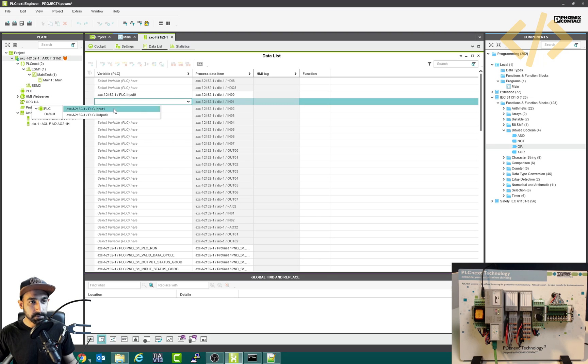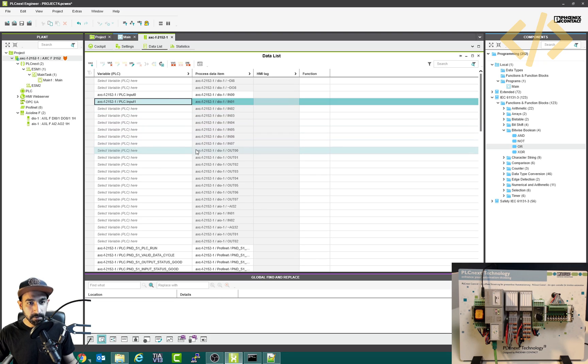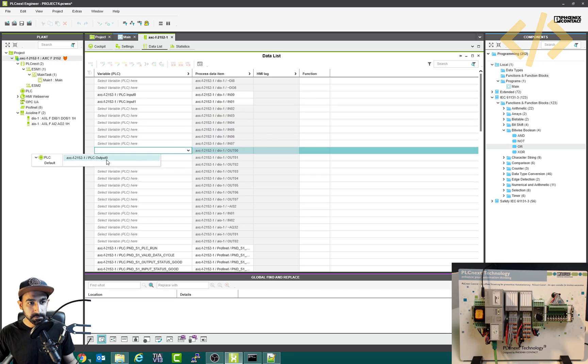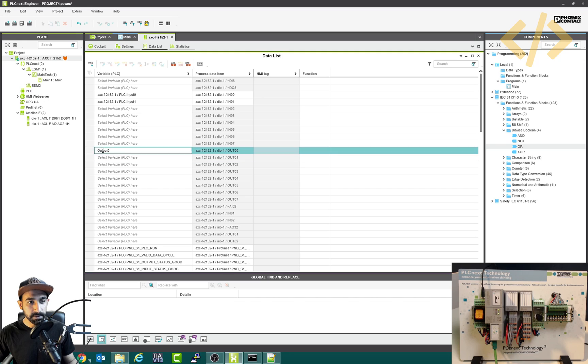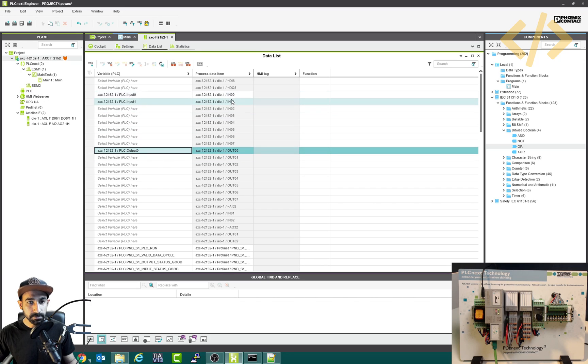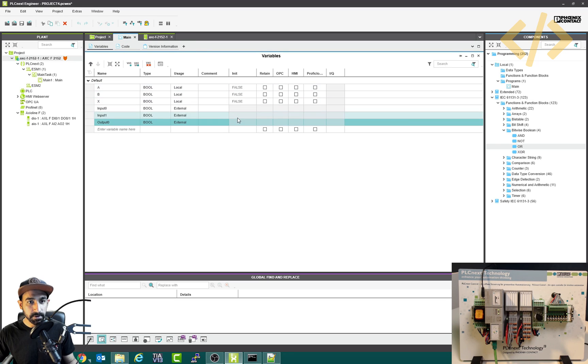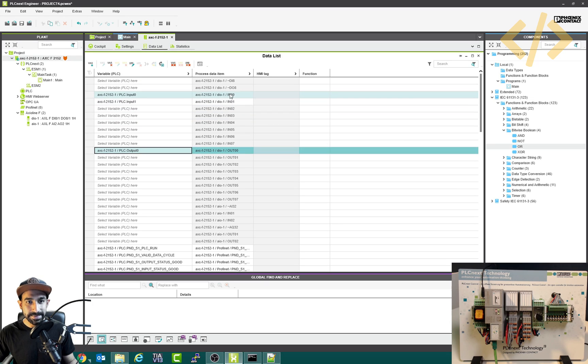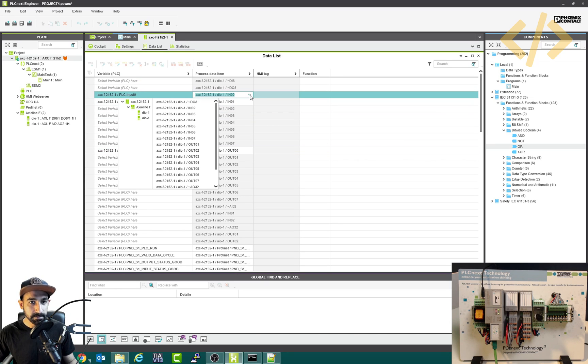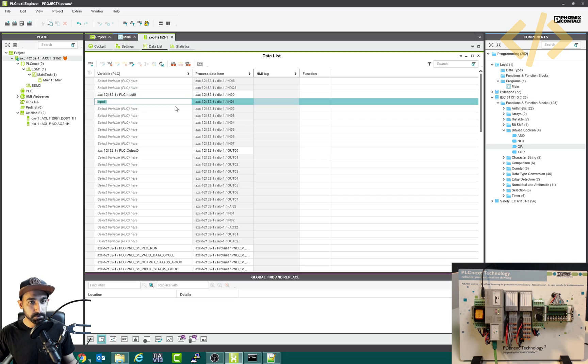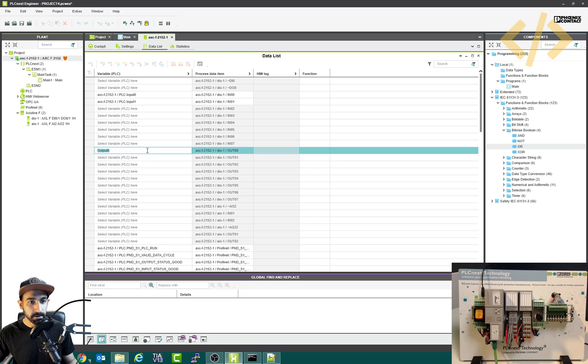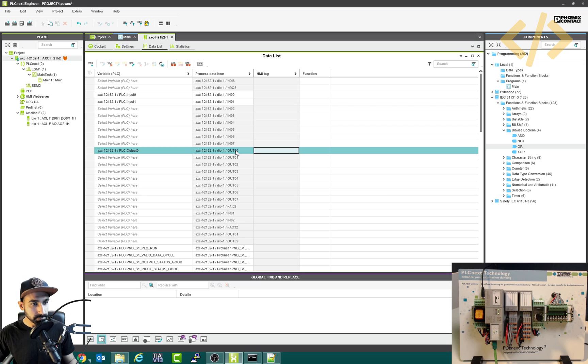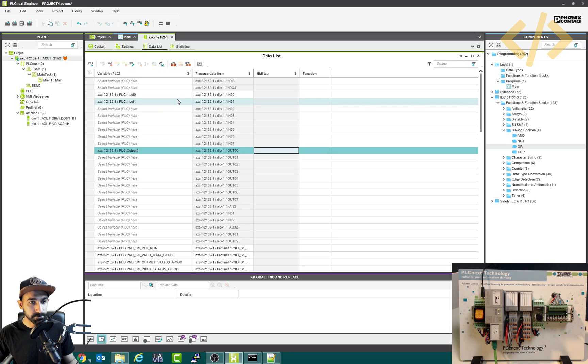Similarly, this is input one. And now we have output zero, which is this one. So we have three variables now which are linked to external IOs. Input zero, which was in my PLC program, here input zero, it's linked to IN zero of external module. Similarly, input one to IN one and output zero to external output zero. That's it. That's how you have linked inputs and outputs.